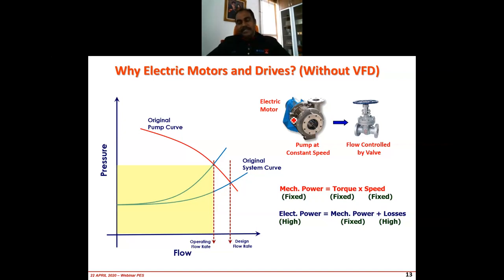You know that a pump system is usually used to transport a liquid, for example water, from one place to another. And usually the pipe system will have what we call a valve, a mechanical valve, to control the flow. So when you look at the curve here, this is the pressure versus the flow. The red line here is the pump curve. When you are selecting a pump, the pump manufacturer will give you this curve, pressure versus flow.